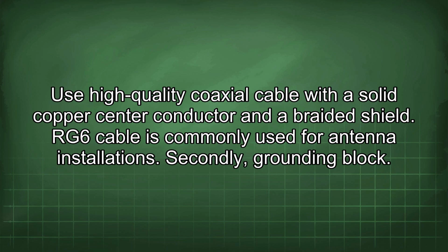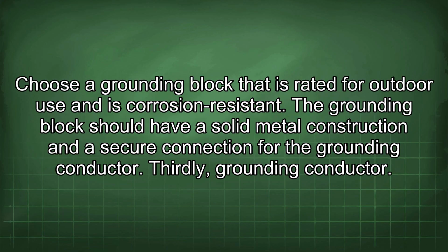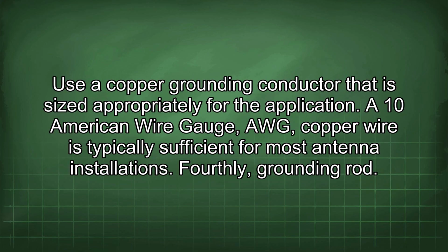Secondly, grounding block. Choose a grounding block that is rated for outdoor use and is corrosion resistant. The grounding block should have a solid metal construction and a secure connection for the grounding conductor. Thirdly, grounding conductor. Use a copper grounding conductor that is sized appropriately for the application. A 10 American wire gauge, AWG, copper wire is typically sufficient for most antenna installations.